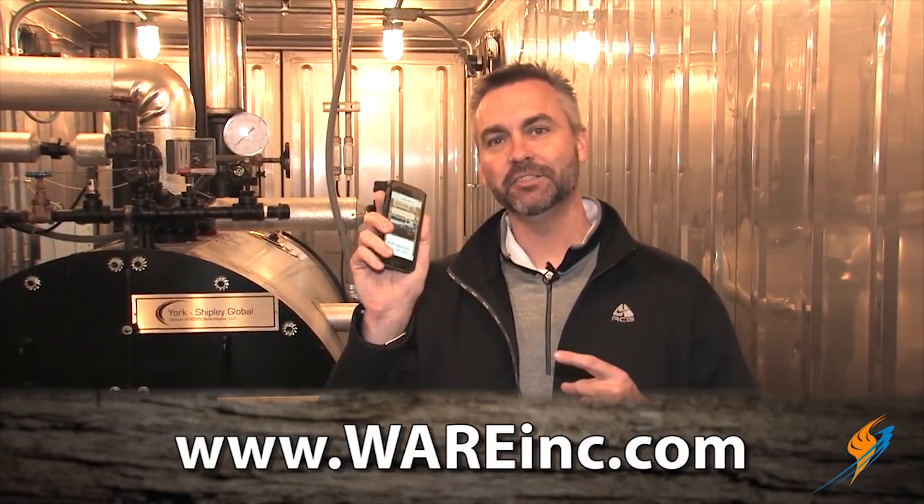Appreciate Michael stopping by and talking about weekly boiler maintenance. Boiler equipment failures can be dangerous and typically result in lost productivity and revenue. Scaling a boiler on the water side will cause overheating and result in a boiler failure. When this occurs, there can be catastrophic failures resulting in water-side or fire-side explosions, with serious consequences including injuries and facility damage. With the right preventative maintenance plan, these issues can be avoided or greatly reduced. Make sure you like us on Facebook, follow us on Twitter, subscribe to our YouTube channel, and if you like our videos, please share them. We also have a new mobile website, so please check it out. We'll see you next time on The Boiling Point.